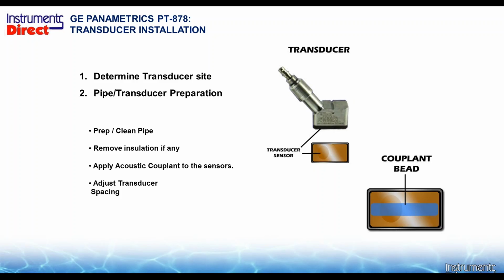You do not need to take the rust off. If you rub it and it doesn't come off, that's fine. That's typical for most installations. Now, as far as the communication between the sensor and the pipe, we need an acoustic couplant. And basically, why do we need an acoustic couplant? We need something to transmit the sound through.